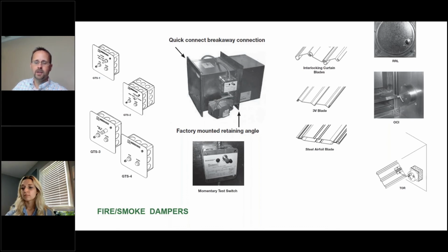So if you have a fire alarm contractor, talk to them to see their preferred test, whether they're providing the test switches or they need them provided with the damper, and then coordinate with the owner the location of those. Some owners like those in the ceiling, so they don't have to get above the ceiling to test it. Others want it in an accessible location. So that's another coordination thing to make sure that the entire design team is on the same page.